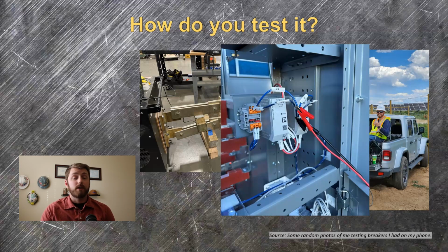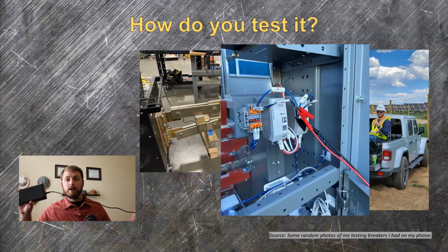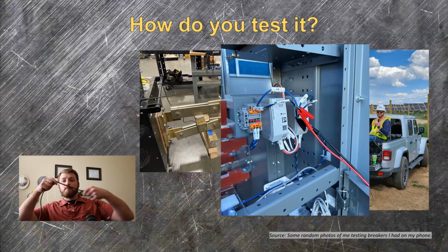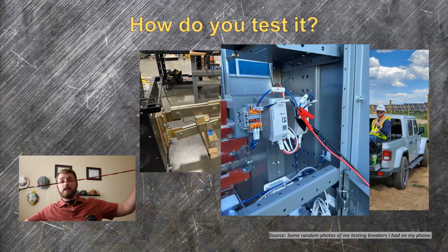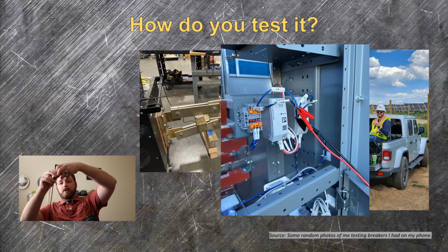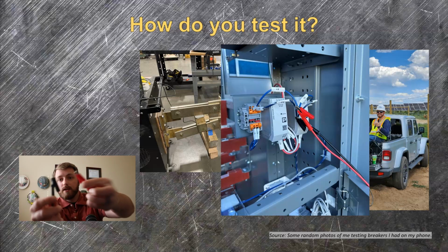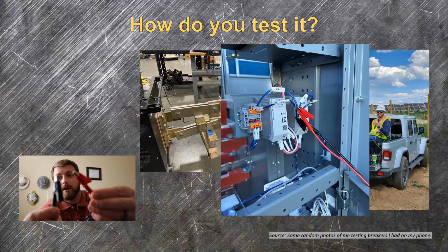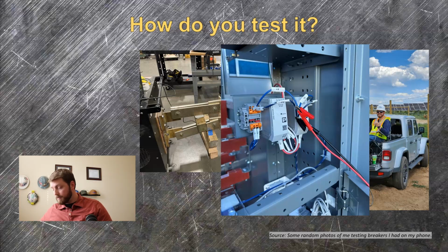If this is a bolt-in breaker that you're going to be testing in situ, I found the easiest way to do this is to take a small 24-volt wall adapter or like a laptop charger, and just lop the end off and use alligator clips to wire it right up to the output of the power supply. I've got one that I use. This is literally just an old laptop charger at 24 volts. I got this really nice long lead on that. You split them apart, get some alligator clips. It makes it really easy to clip right up to what you're working on.